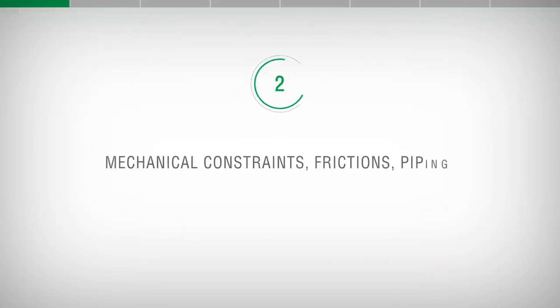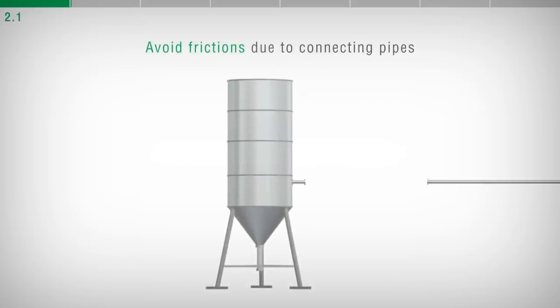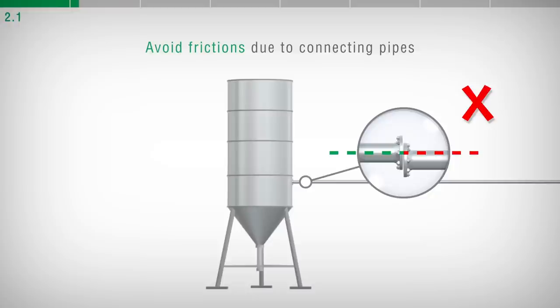Mechanical constraints, frictions, piping. The more a weight structure is free from friction, the more a weighing system is precise. When piping are present, make sure that the pipe to be anchored to the weight structure is close and aligned with the nozzle to which it will be clamped.